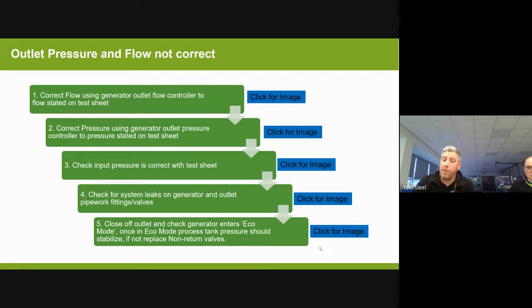We're going to check for leaks in the system. If there's any leaks, they have to be repaired, obviously. But then what we're going to do is run the system, and we run the system until it reaches its designated purity. That shouldn't take too long, maybe an hour or two. Then we're going to close off the output from the system. This is all detailed in the service manual.